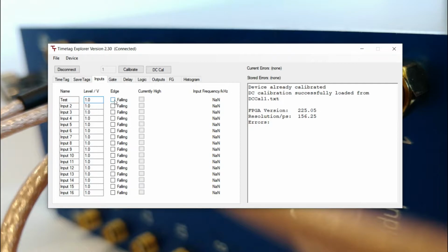Note that for our test case, the function generator is simulating the photon detection signal and is a TTL pulse with a 2.5 volt high level into 50 ohm termination, so a 1 volt threshold is fine.